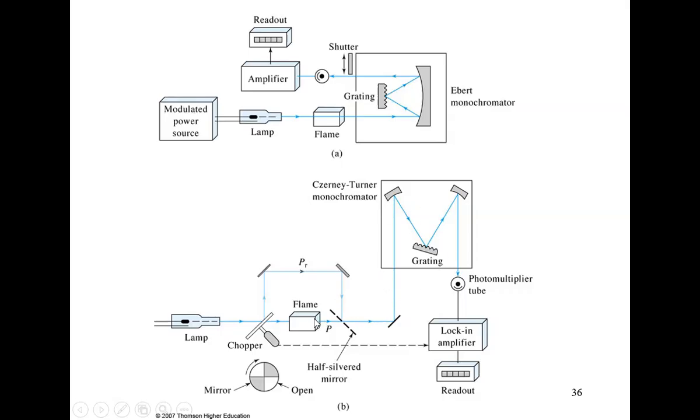Notice, initially, when you do your analysis, like when you did the UV, you put two cuvettes on the reference and the blank, remember? You used acetonitrile. That was then taken digitally, taken into memory. Then you put your samples here, and it keeps referencing the original blank sample. This is a double beam, as you see.